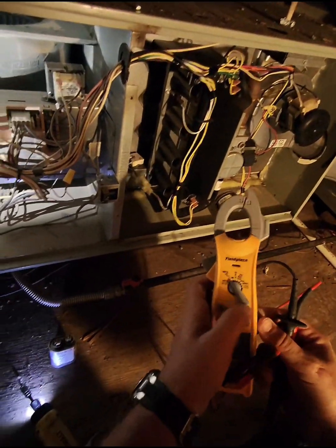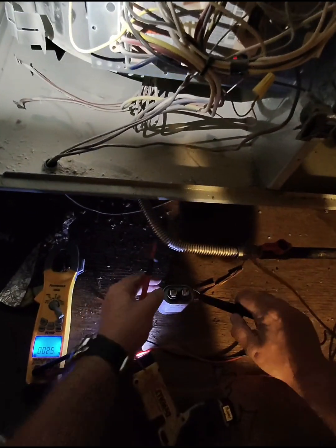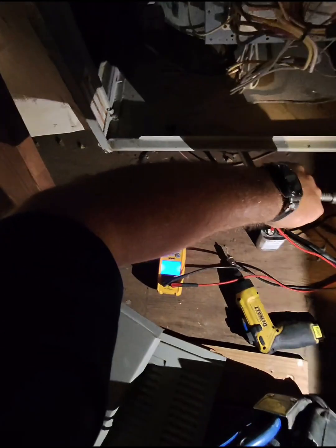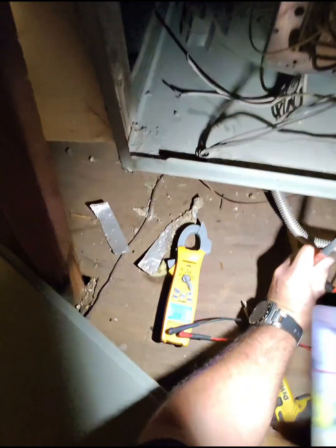Check our capacitor here. 10 microfarad. Alright. Any time you take electrical connections off, I always like to retighten them a little bit and inspect them. Make sure you've got no cracks or anything in here, because that can create some issues. Then you also want to do the tug test.